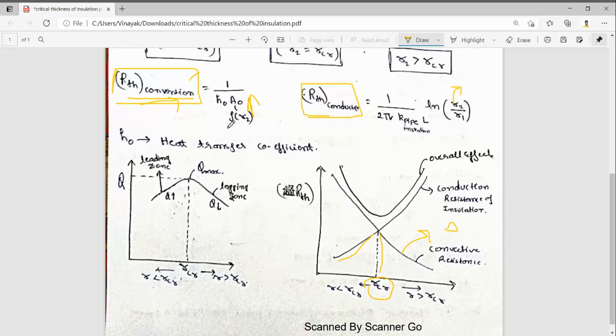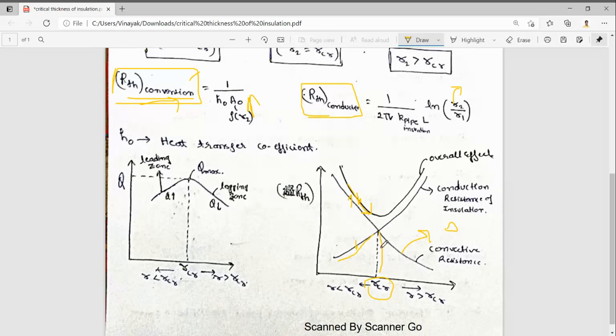Before the critical radius, heat transfer will increase because the resistance is very less and decreasing. Up to the critical radius, as resistance is decreasing, the heat transfer will increase. But we are keeping insulation so that heat transfer should not occur, so this is counterproductive. After the critical radius, the conduction resistance of the insulation comes into picture and increases the thermal resistance, so heat transfer will decrease.